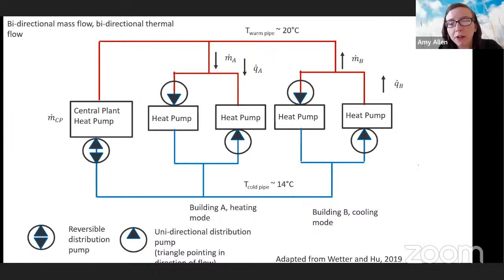And work by Wetter and Hu, and also a study by Sulzer, which was focused on the 5G DH system at ETH Zurich, has revealed practical problems in control of circulation pumps in systems with this two-pipe configuration, which resulted primarily from conditions of low load at the connected buildings, in which case a control valve would modulate to reduce the minimum flow from a circulation pump, which is likely oversized, which could result in control instabilities propagating among the connected loads since they are hydraulically coupled.